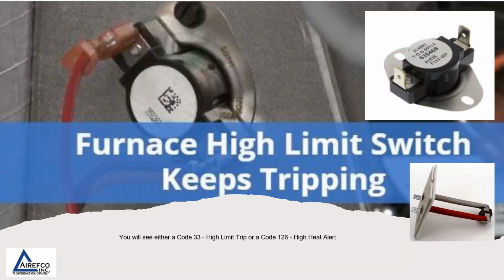So when a high limit switch trips, you will either see a code 33 for high limit trips or a code 126 for a high heat alert. When these limit switches trip, they will shut the furnace down, and if they continue to trip, they will be a nuisance for the homeowner, and a technician will be called to try to diagnose what's going on.